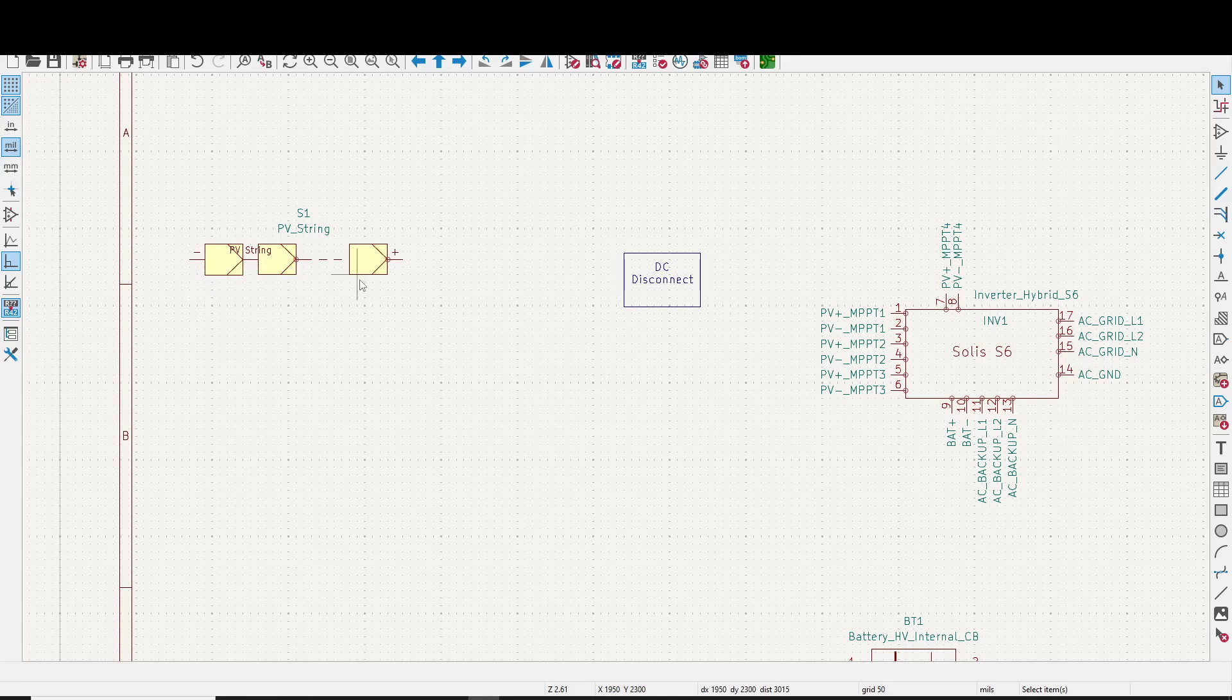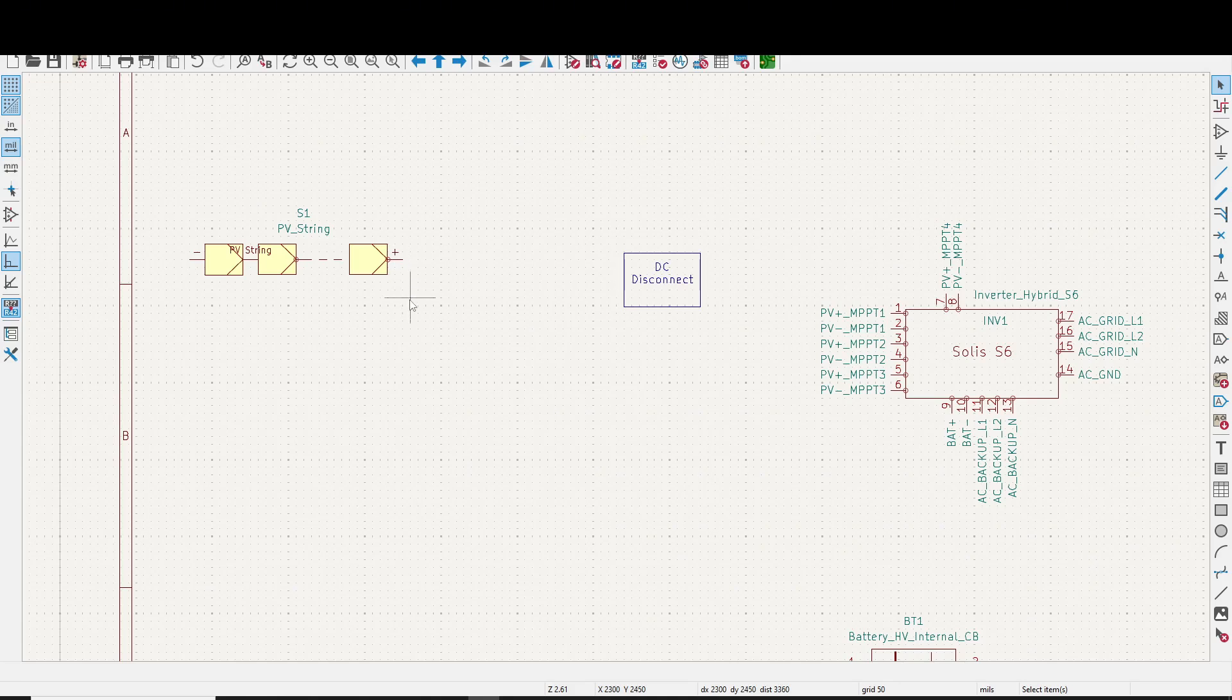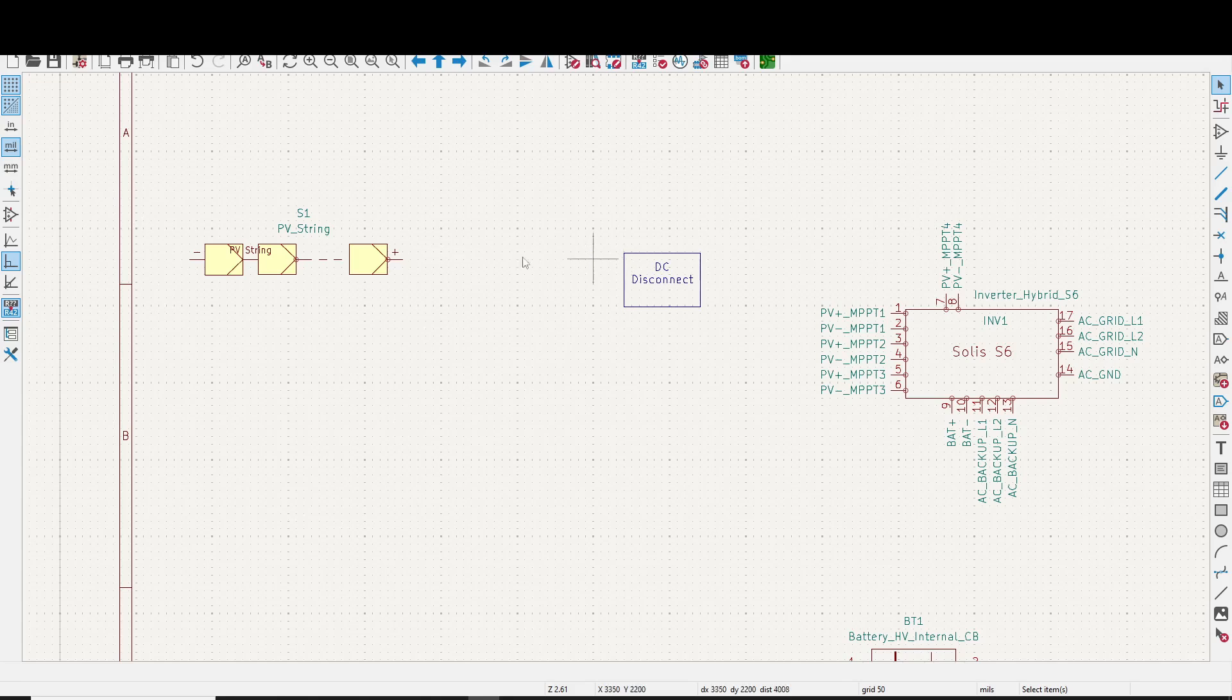Okay, and the string has to be sized for your inverter. For example, the Solis S6 has a maximum open circuit voltage of 600 volts. So this string of solar panels can't be over 600 volts. It's got a start up voltage of 80 volts. So if you put some panels together that are only 80 volts, that'll start the inverter up. The max current is 16 amps, and the short circuit current is 25 amps.